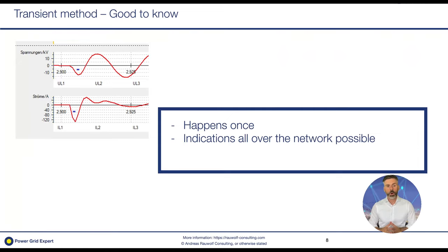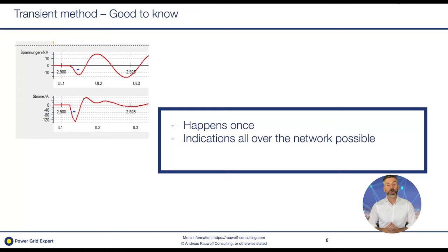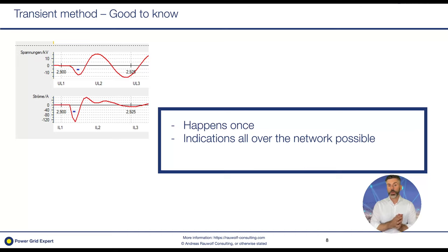It is important to know that the transient only occurs at the very beginning of the earth fault and does not happen again. Especially if you are using earth fault search methods like shifting the normally open point, the transient method will not trigger again. Also, as with all earth fault methods in compensated and isolated networks, indications may occur all over the network — not only in the faulty feeder — but in those other cases they will point toward the direction of the fault location.